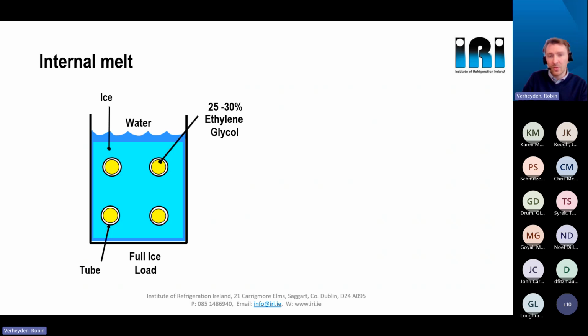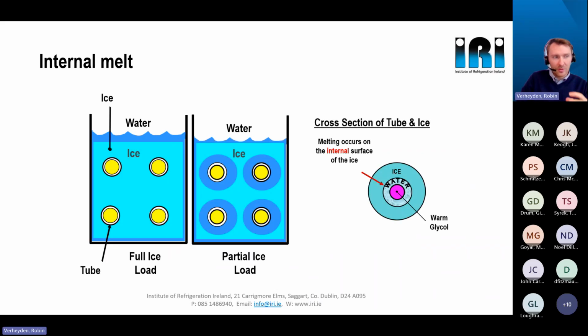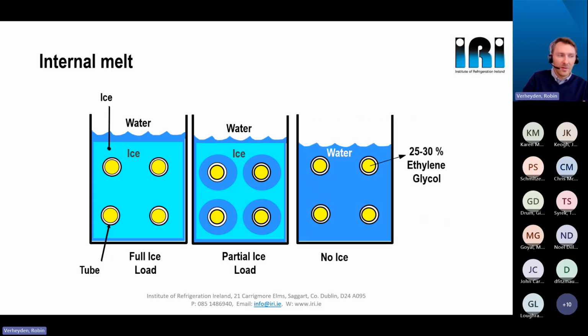Now let's have a look at how this works. As we discussed in a previous slide, we will first build the complete ice block via cold fluid going through the tubes, through the coil. The complete ice block is formed. Now we will pass water, for example 11 to 6 degrees, through the coil, and we will start melting the ice from just around the coil, from the inside of the ice block outward to the barrier. And we do this until the complete ice block is melted down.